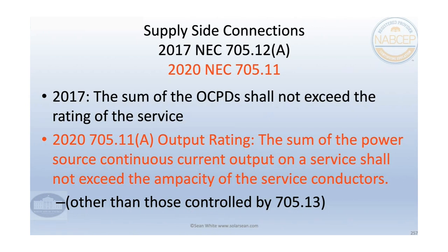Another thing, speaking of energy storage systems, is a good reason to skip over 705.11, which is supply side connections. They changed it from 705.12(A) to 705.11. If you're going to do backup, you do not want to connect to the supply side, because if you do a supply side connection, you are not backing anything up. You need to be on the load side of a main service disconnect with overcurrent protection. And so that would be a load side connection.